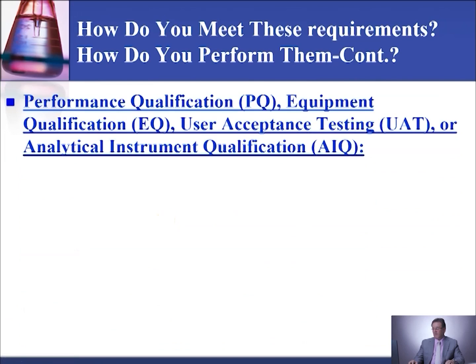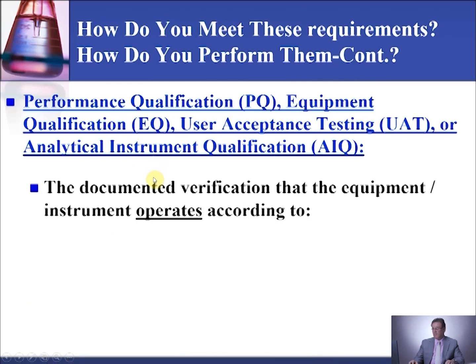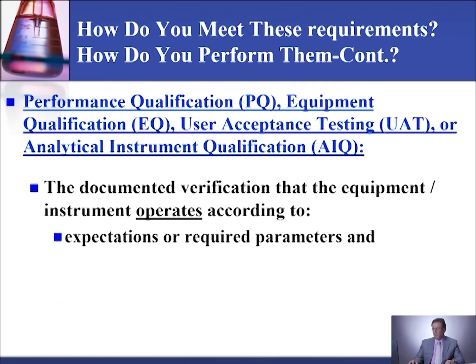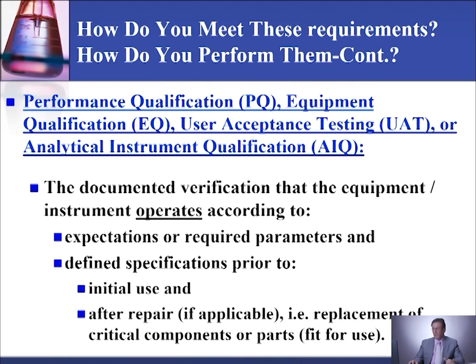So, performance qualification. Next, we're going to talk about performance qualification, equipment qualification, user acceptance testing, UAT, and analytical instrument qualification. All these things mean the same thing. Okay? It is the documented verification that the equipment or instrument operates according to expectations or required parameters and defined specification prior to initial use and after repair as applicable, like a replacement of a critical component or part.